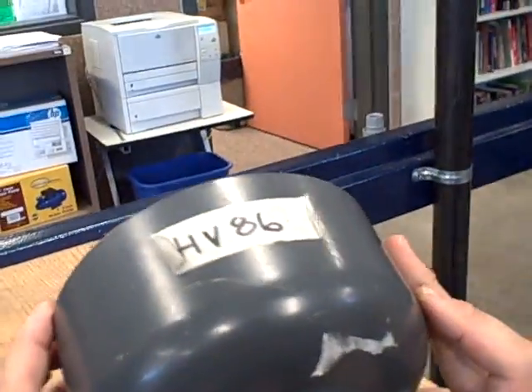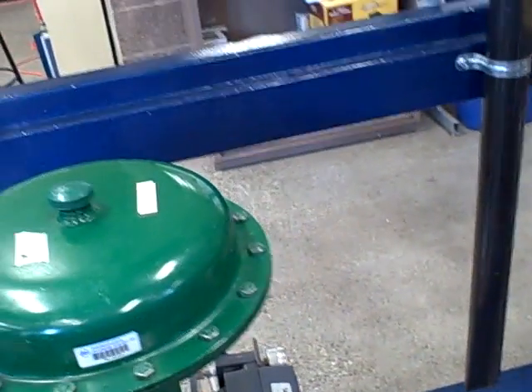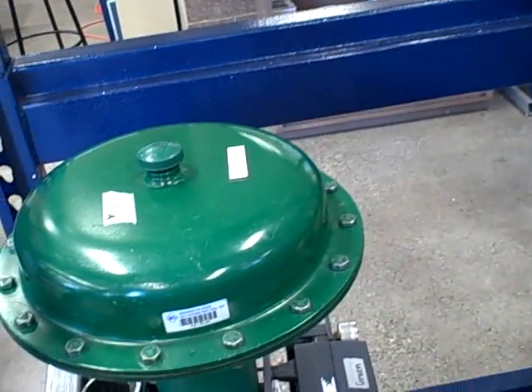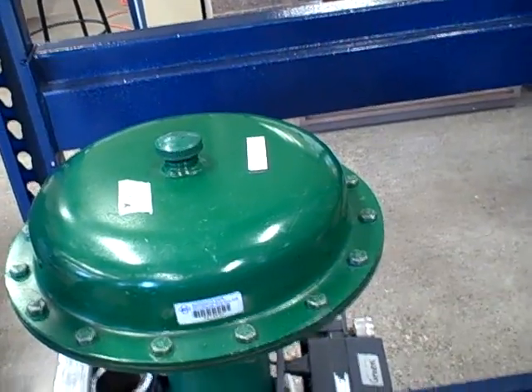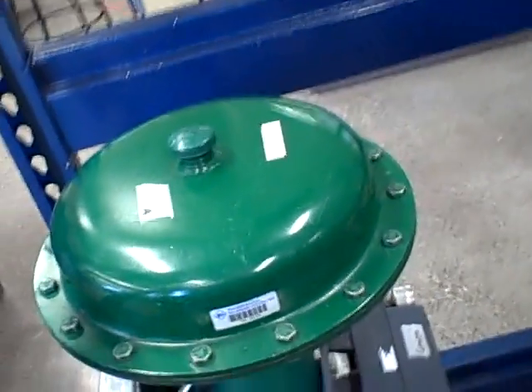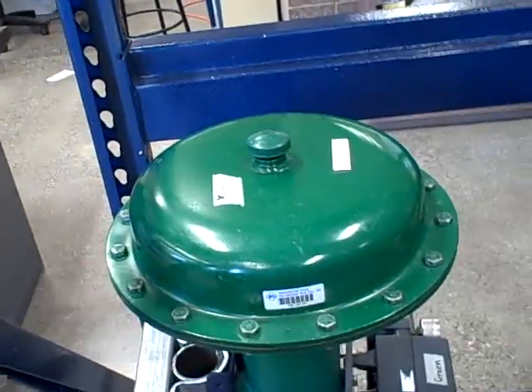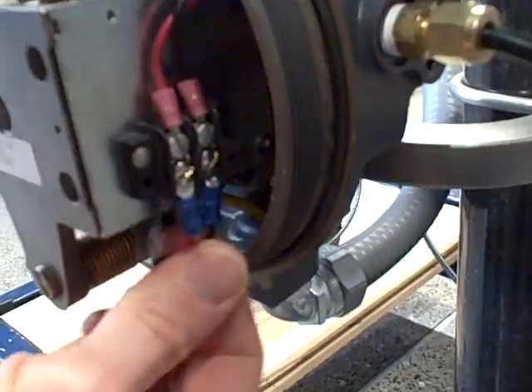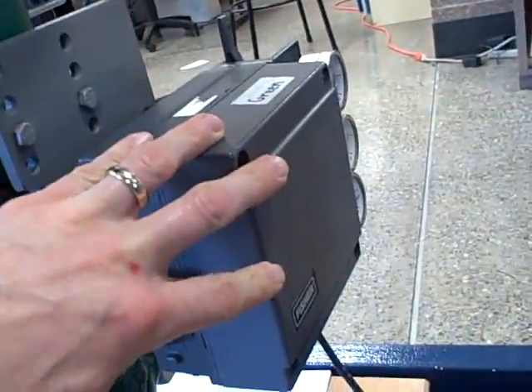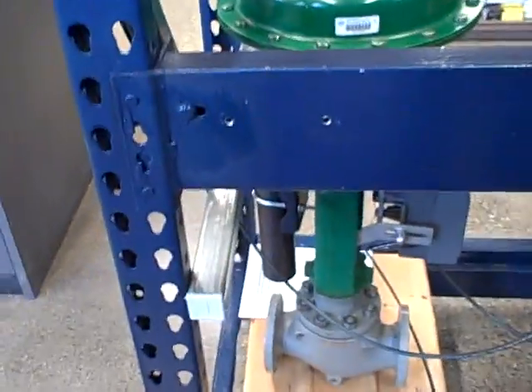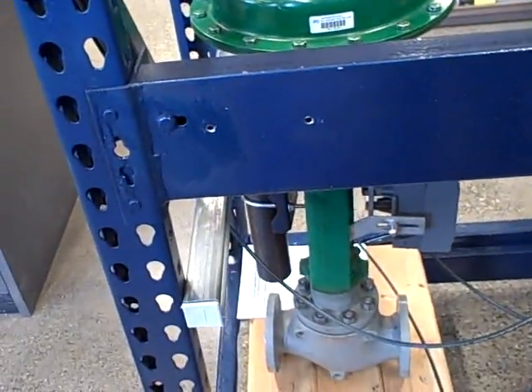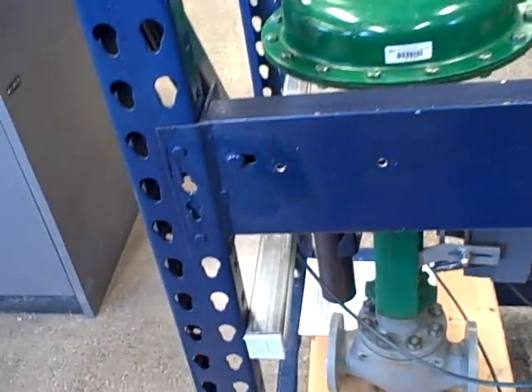Ah, okay. We have a wrong label. We have to change that. We have a wrong label on that. Here we can make a temporary change. It's not the color. No, actually, I gave the marker to Deb. There you go. Okay. And down here, I'm going to check our wire terminations, make sure everything looks good. I don't see any problems with that. Okay. That's our I2P sending air pressure to our Fisher 3582 positioner, which then goes to our Fisher control valve. And that concludes the wiring and the tubing for HV85A.